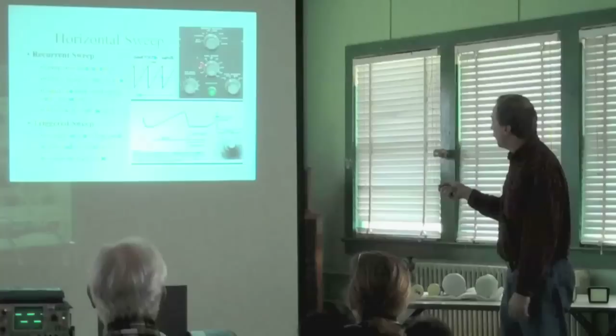The problem with that, number one, is it is uncalibrated, so I can't make precise timing measurements. But I can look at relative wave shapes, no problem. But I can't really make precise timing or frequency measurements by looking at it. The other problem is that because it's continuously free-running, if I want to look at an input waveform, usually that input is not going to be synchronized to the sweep speed. And the waveform looks like it's rolling back and forth or swinging back and forth. It's kind of a big fuzz across the screen. It's not locked like we're looking at right here, because the horizontal sweep speed is not necessarily going to be exactly the same or harmonically related to the signal that you're looking at.